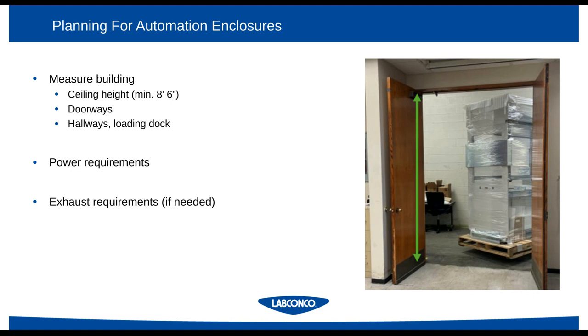Also want to talk about exhaust requirements for those of you who may be handling solvents or other things that may require exhaust. The Logic Vue can be exhausted just like most biosafety cabinets, and to do so, it's really important to evaluate the mechanical system. Due to the size of an automation enclosure, there's a high volume of air that is exhausted throughout the system, and accommodating that on the building system and its exhaust is really important to evaluate before purchasing the equipment.